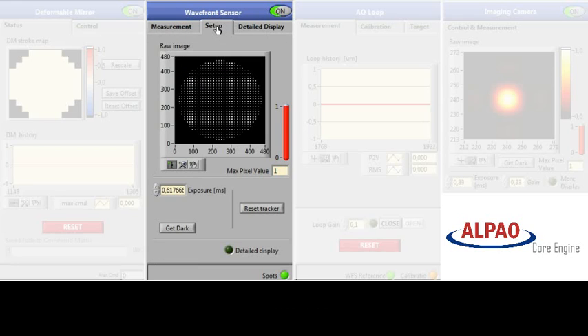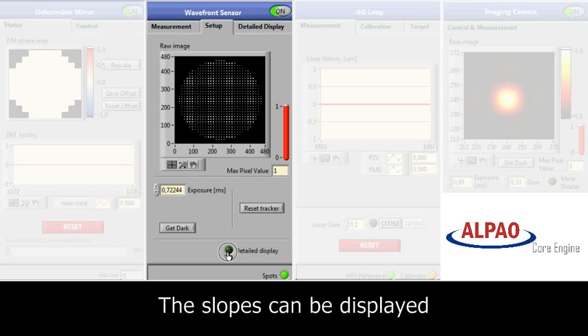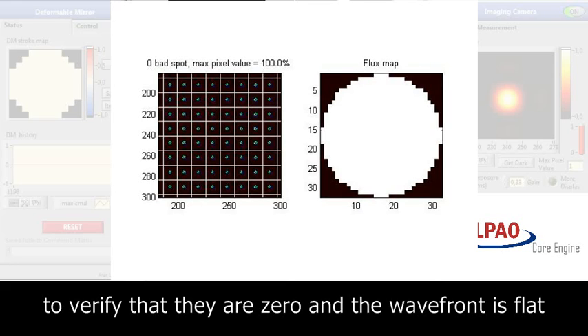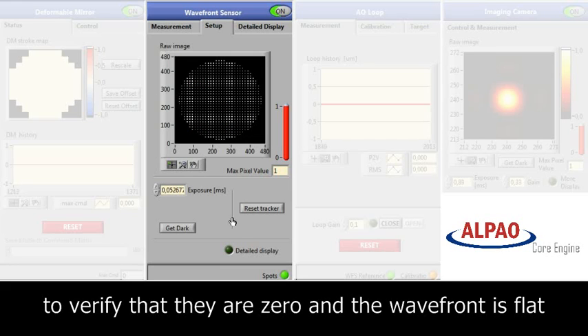Here we can see a detailed display of the wavefront where we can verify that the wavefront is flat by either looking at the spots or verifying that our slope matrix is zero.